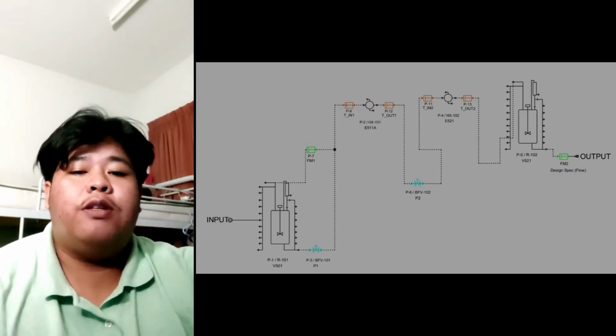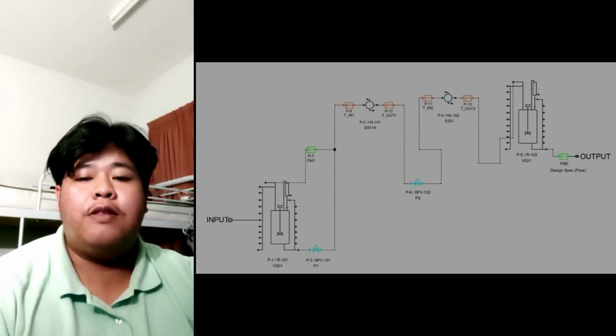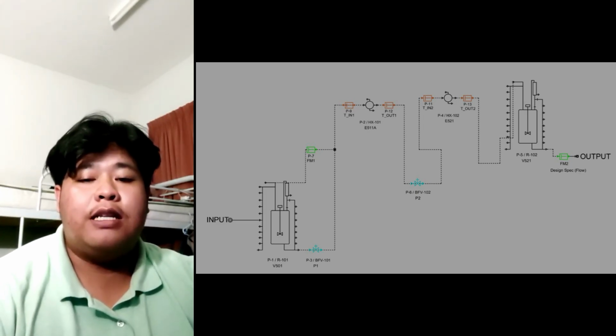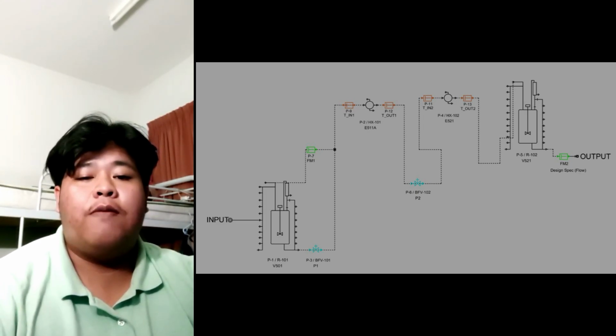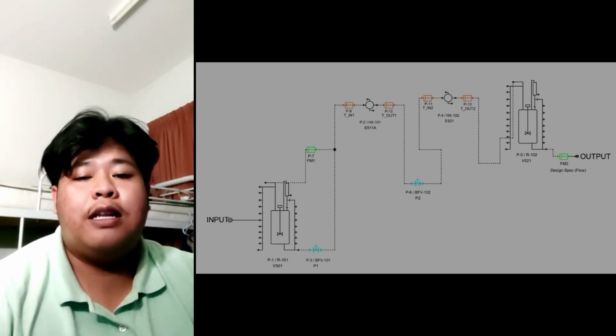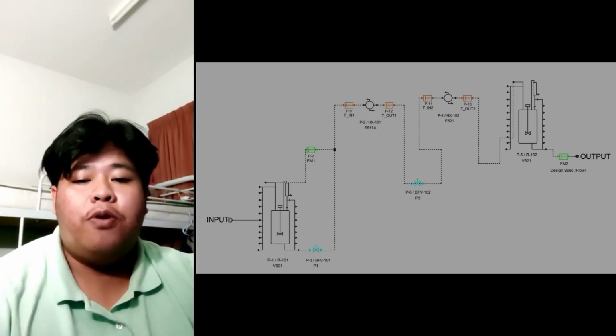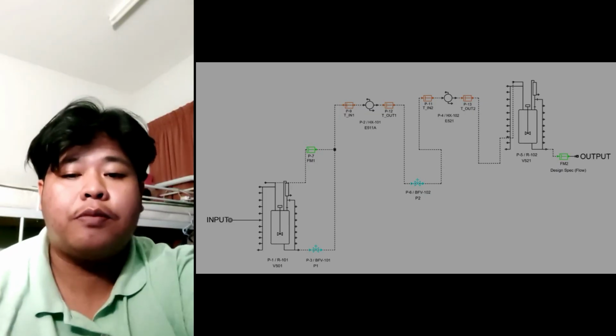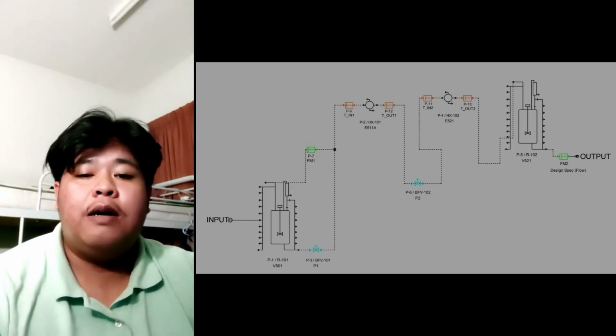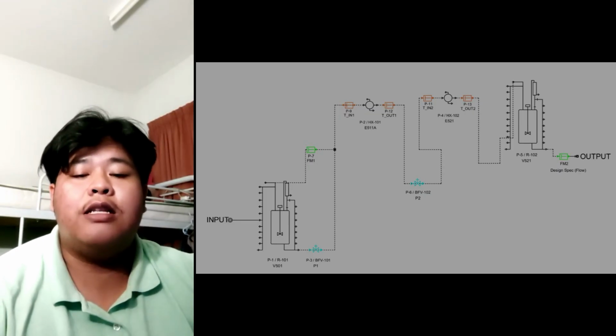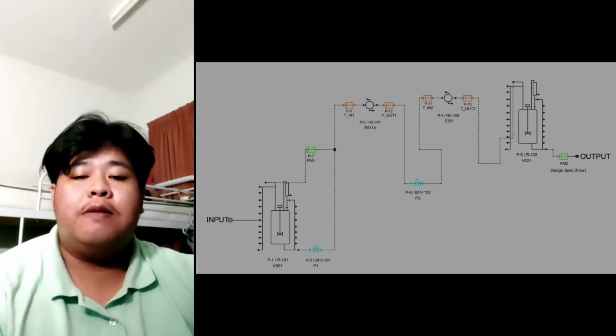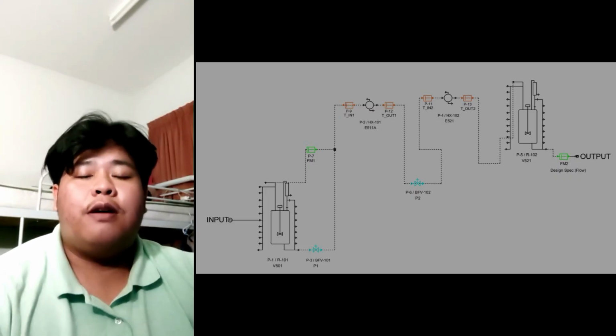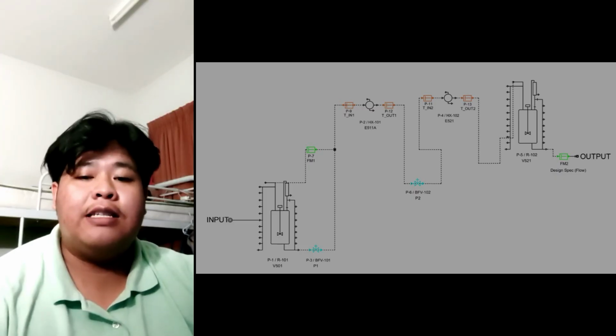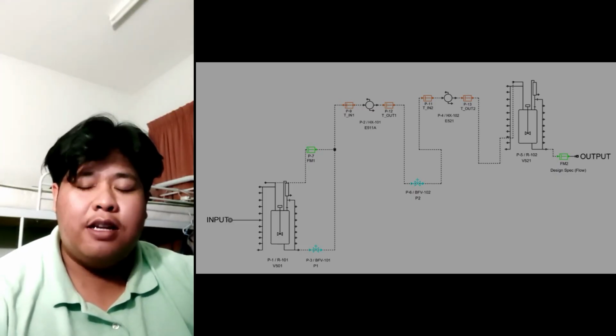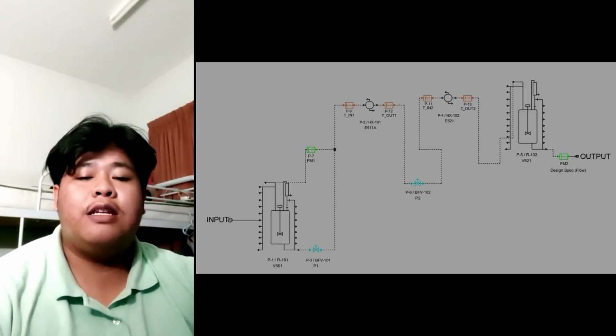So why did we choose this specific configuration? Manual valves cannot compensate for sudden changes. By using the feedback from FM1 and FM2, the system automatically corrects disturbances, ensuring the output meets strict design specifications. Previously, the pump might run at full capacity regardless of the demand. With this automated system, if the thermal load at E521 decreases, the valve restricts flow and the system consumes less energy for pumping.